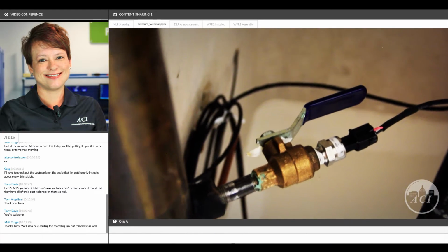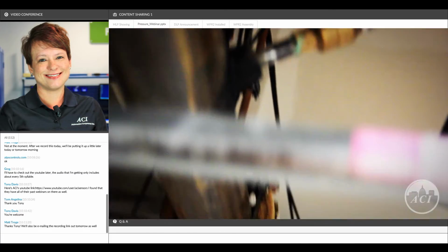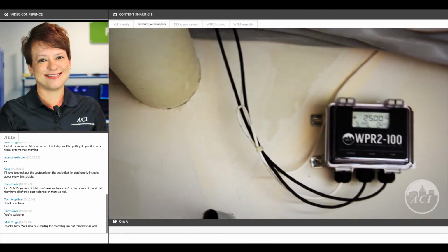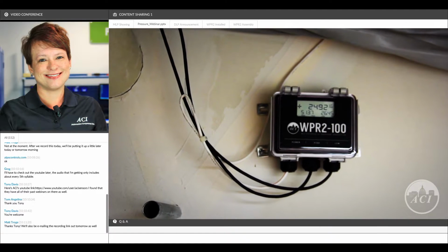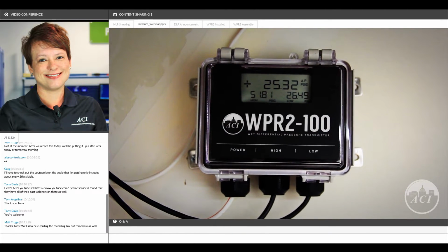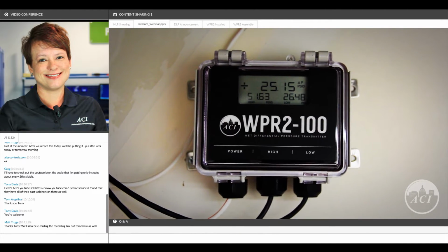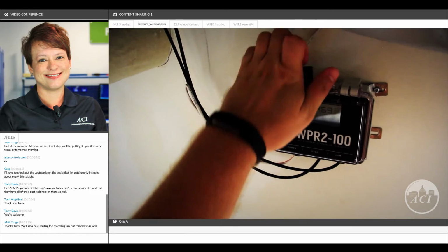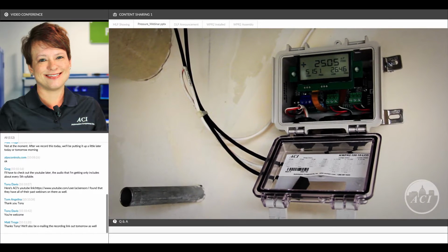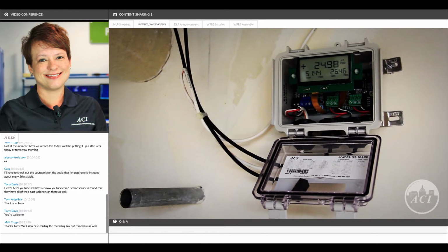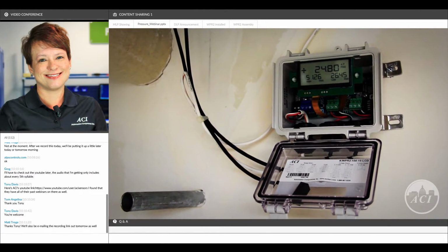Our standard lengths are 10 feet. We have a 20-foot option available. Here you see the unit. With the big LCD display, you've got your differential pressure, your high side and your low side showing. And then here is the hinged cover, which allows easy access inside if you need to change your pressure setting, perform an auto zero function, adjust your output, whatever the need may be.